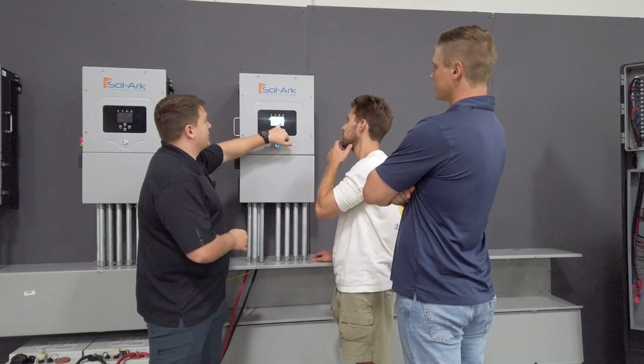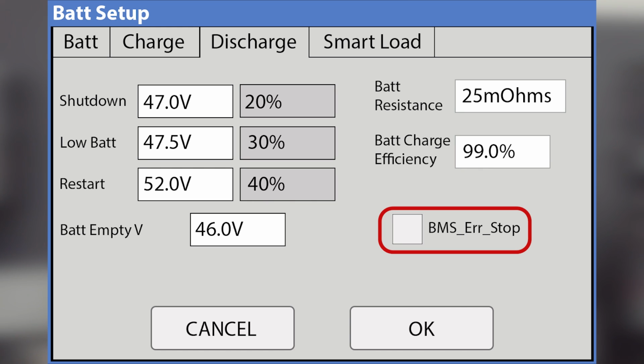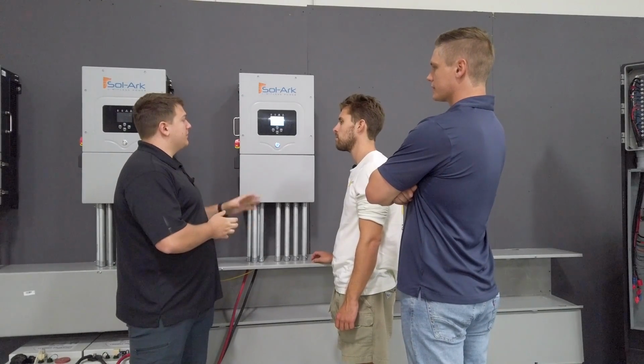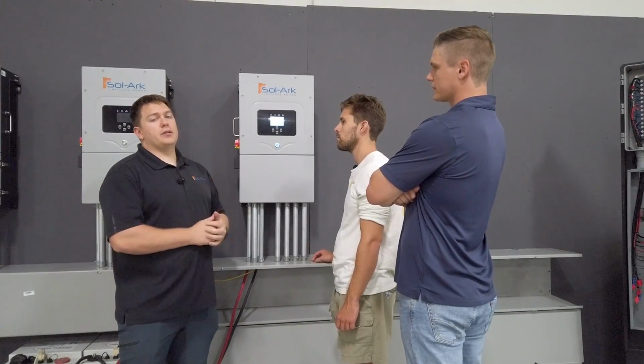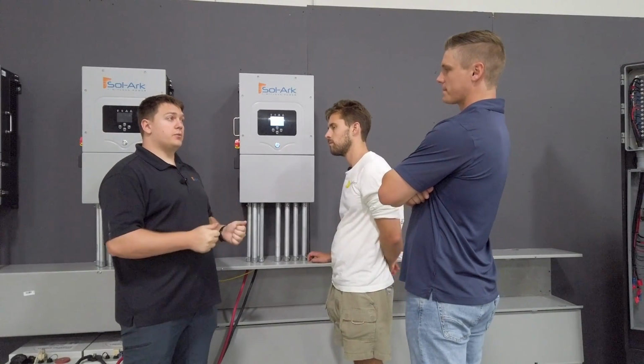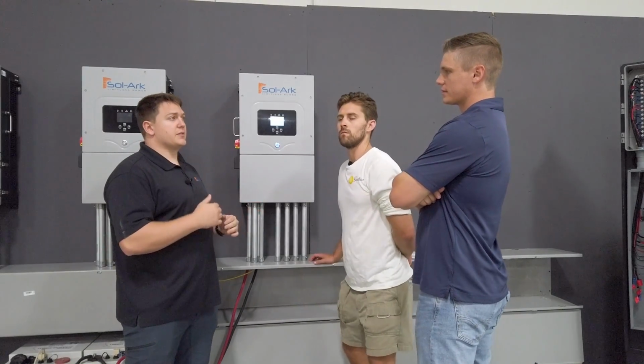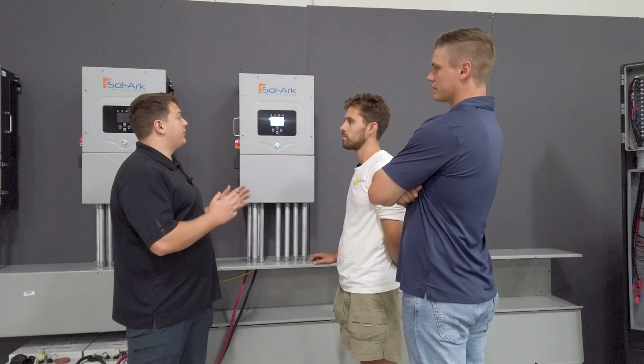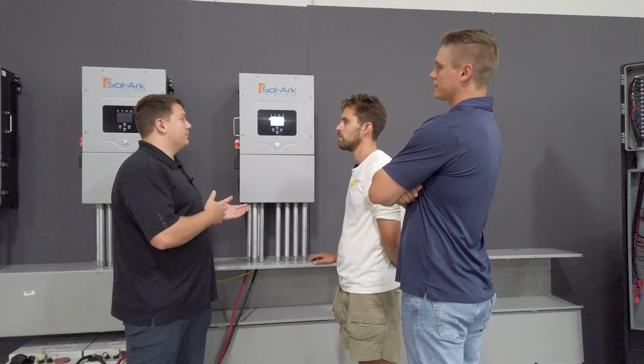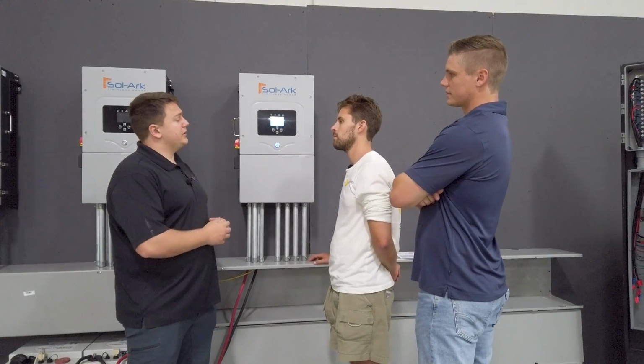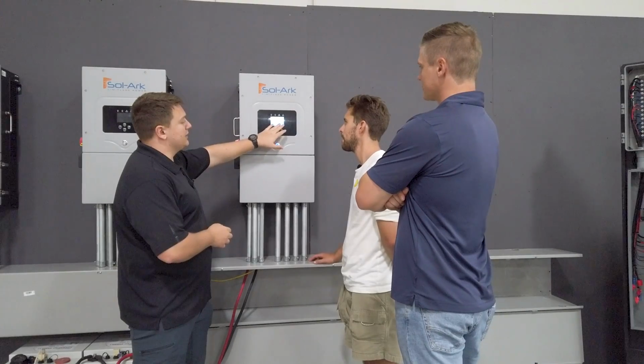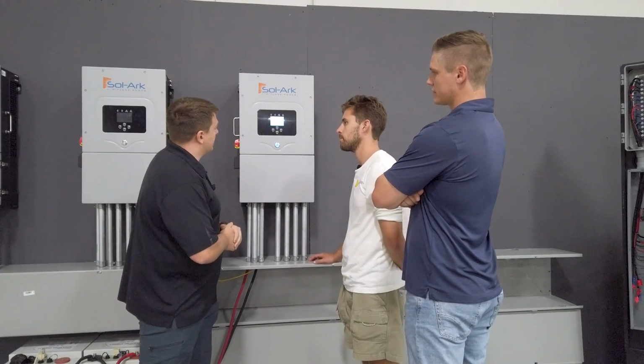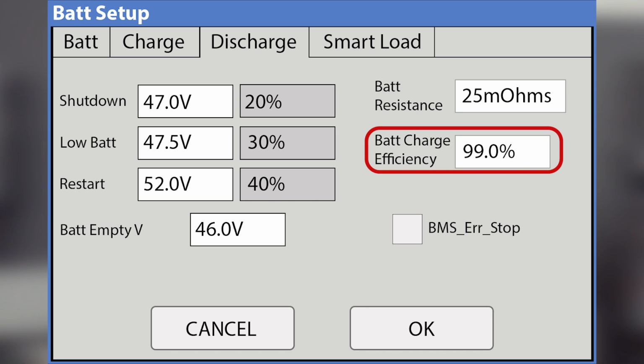There's also, and this is actually a really good one too, the BMS error stop. If you have that enabled and your BMS has communications with the system and there's a blip in the communication, if that's on, it'll shut the inverter down as an alarm. Usually you don't want that. The reason we're going through all these battery settings now, even if you have a lithium battery that tells the inverter what settings it needs to have, which is cool, is that you still want to do this manual process also, because if the communications ever lapsed for any reason, it's going to default to whatever it was programmed to. So if it's already programmed to the right settings and there's a blip in the communication with the battery, you don't need to throw an alarm, everything's okay. So usually we'll just leave that off if you've done the proper programming ahead of time.